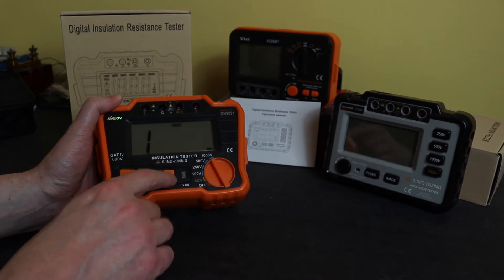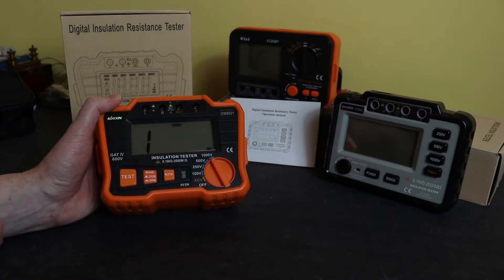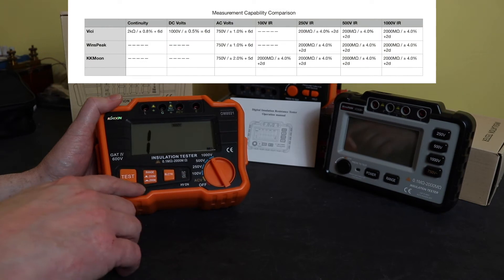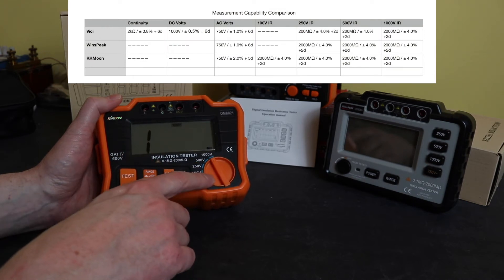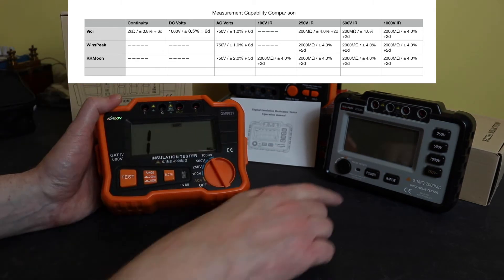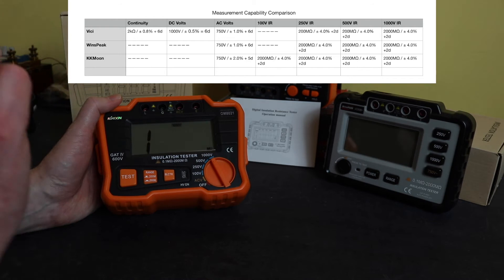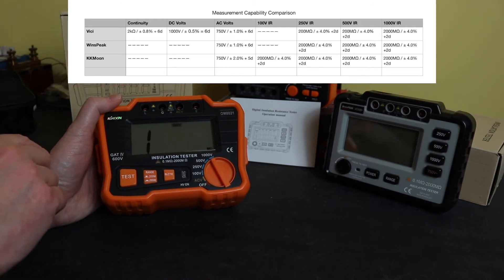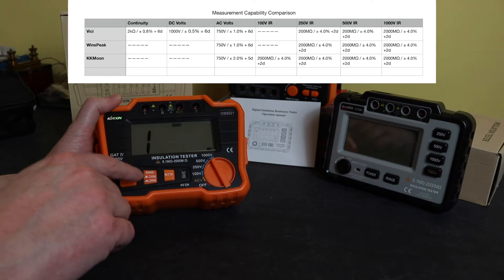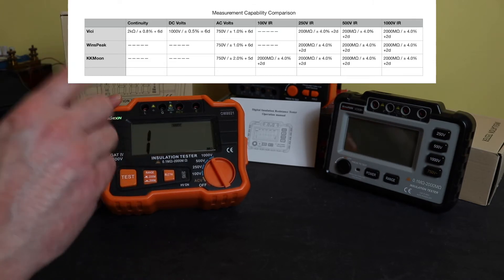The backlight is manually controlled on the button here so you can turn it on and press it again to turn it off. Range is either 200 megaohms or 2000 megaohms — 2 gigaohms — and that applies to all four test voltages. That's similar in functionality to the WinsPeak unit that also has a 2 gigaohm range and a range button to change between upper and lower ranges. Unlike the Vici, which is automatic throughout the ranges but has a limited range — the 2 gigaohm range is only on the 1000 volt, while at 500 and 250 volts you're limited to 200 megaohms.